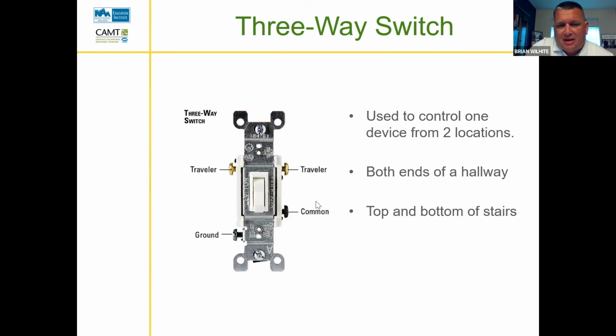And you're right. I think that's named poorly, but now that we've exposed it and we all know that it's the completer of the circuit, or the end of the line where we're going to send our power, I think it makes things easier in figuring out from one box to the other. So if I was at the top and bottom of a hallway, I can identify the common, then shut the power off and put those two wires together that are left and determine which two of those are down on the bottom end of the stairs. Okay, those are my travelers, which leaves this last one as my power. It makes things very simple. Sometimes we get overwhelmed in our own brains and overthink things, but it's pretty simple when we start thinking about it. Any questions on that three-way switch?